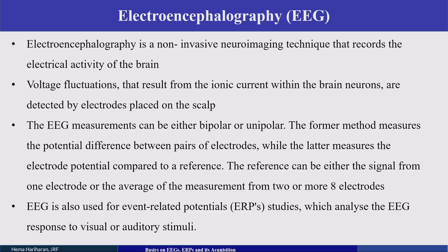EEG measurements can be bipolar or unipolar. In the bipolar method, the potential difference measured is between a pair of electrodes. In the unipolar method, the electrode potential is measured compared to a reference. Any EEG recording will have an active electrode, a ground, and a reference.